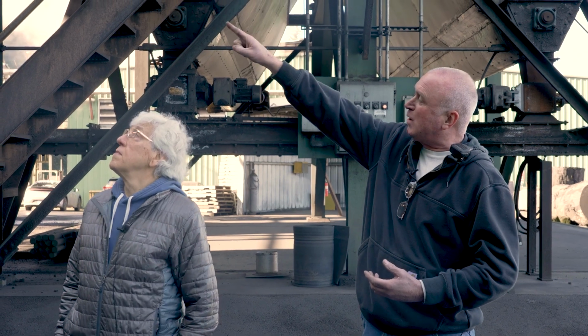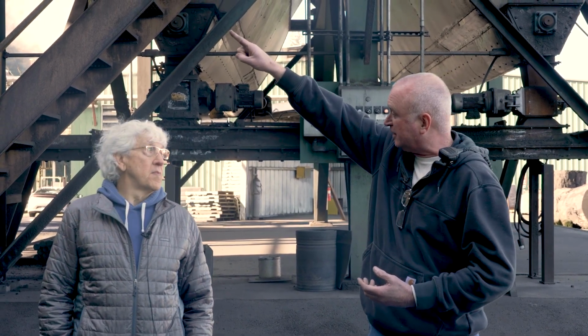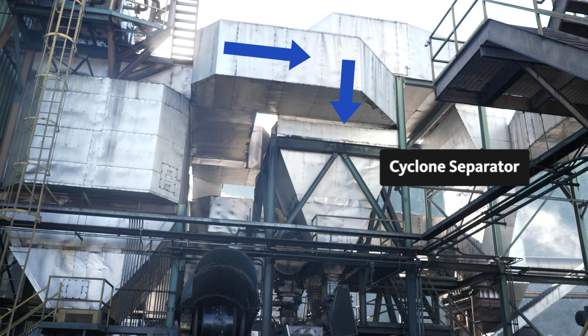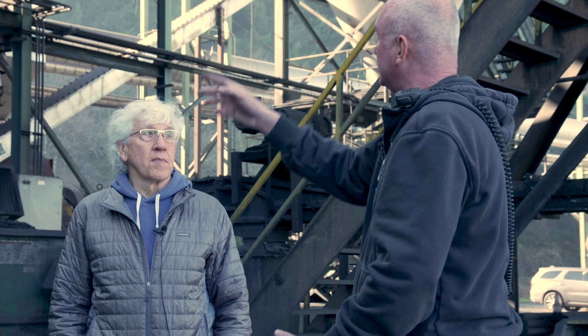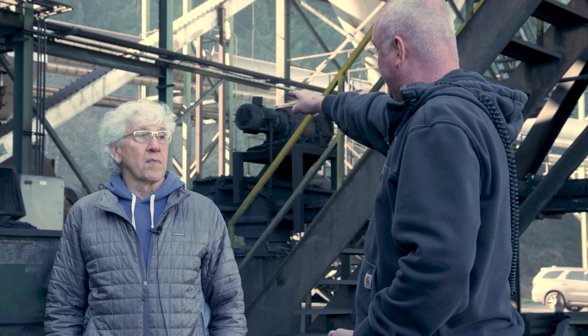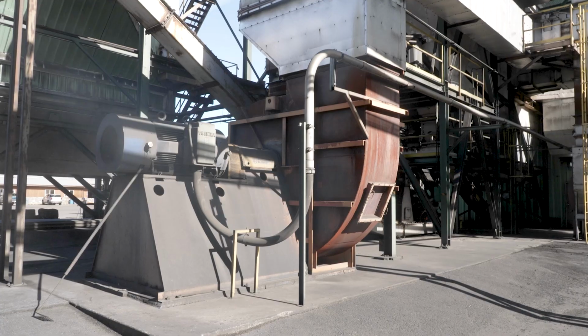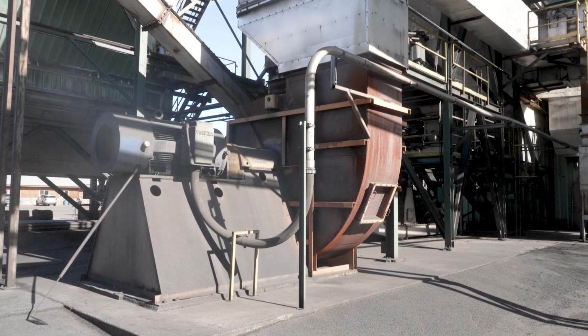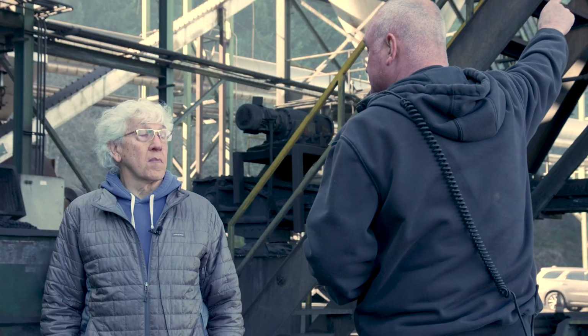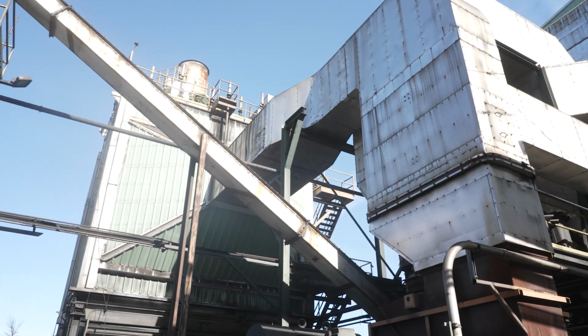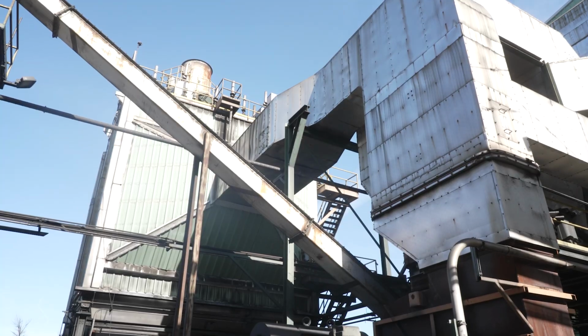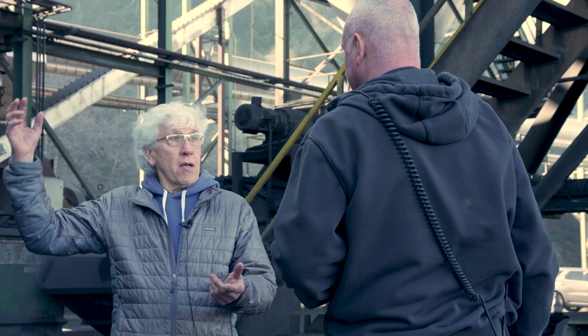Then it travels out into what we call a cyclone separator. A cyclone separator is the first line of defense for particulate emission. What it does is it causes that flue gas to go through a rigorous path, and any heavy material will fall out into the ash system. From the cyclones to the ID fan, induced draft fan. That means it is pulling a negative pressure on the boiler, to the electrostatic precipitator, or the ESP, and then out the stack.